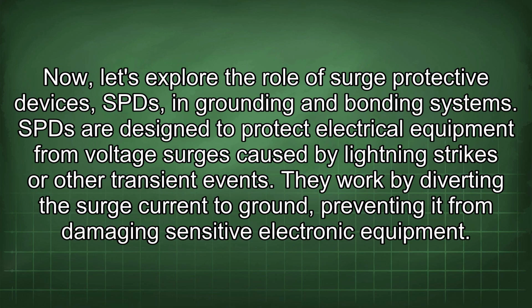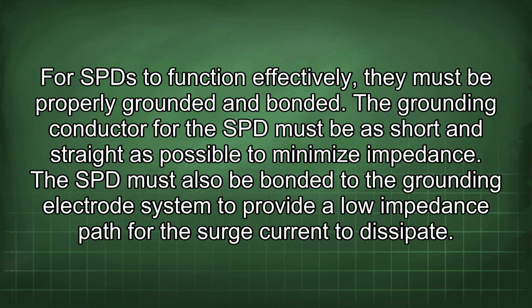Now let's explore the role of surge protective devices, SPDs, in grounding and bonding systems. SPDs are designed to protect electrical equipment from voltage surges caused by lightning strikes or other transient events. They work by diverting the surge current to ground, preventing it from damaging sensitive electronic equipment. For an SPD to function effectively, it must be properly grounded and bonded. The grounding conductor for the SPD must be as short and straight as possible to minimize impedance. The SPD must also be bonded to the grounding electrode system to provide a low impedance path for the surge current to dissipate.